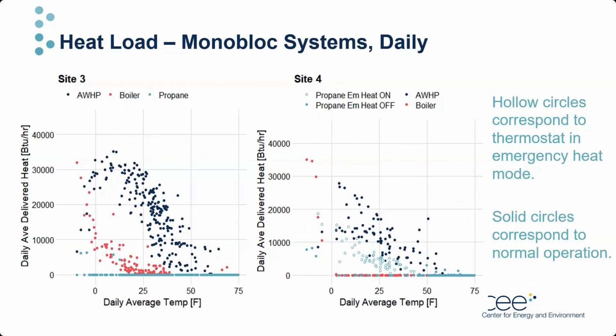This is the same plot this time for the two monoblock systems. The heat pump is in navy, the boiler is still in red, and this time we also have the propane forced air heat delivered in teal. And again, the bin data is on the next slide, but we're looking at the hollow teal circles versus the filled teal circles for now. Site 4 had an extended period of time for which the upstairs thermostat control in the propane system was placed in emergency heat mode, meaning that this thermostat never called for the air-to-water heat pump while the manufacturer worked to troubleshoot system issues at the site.